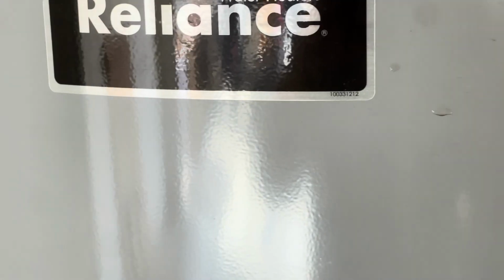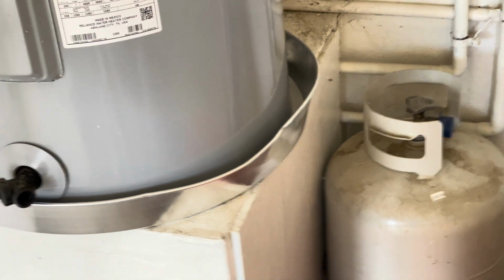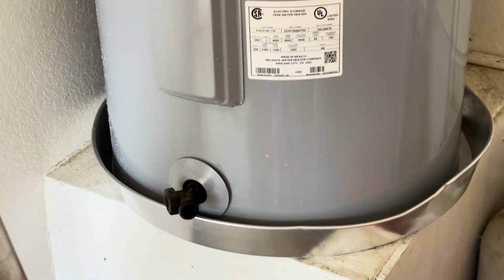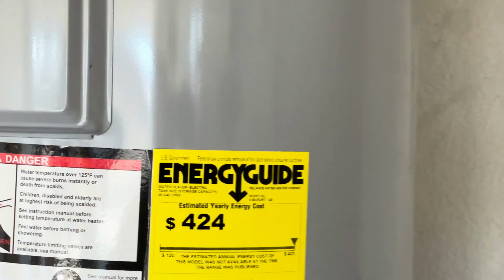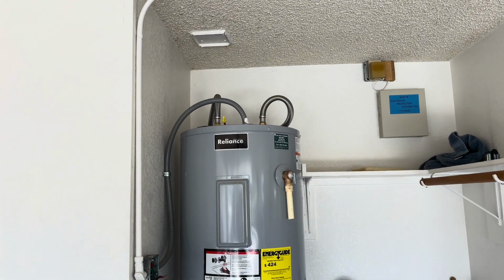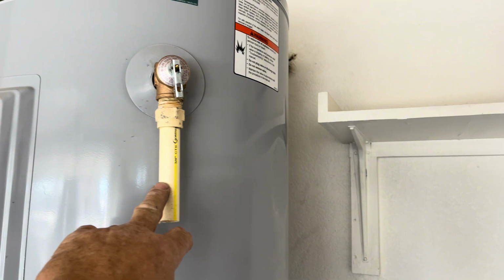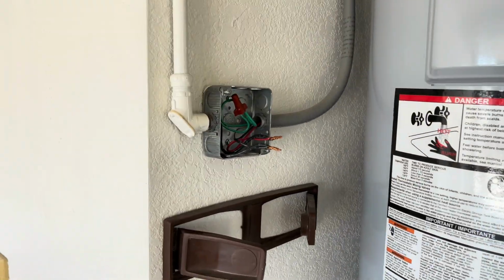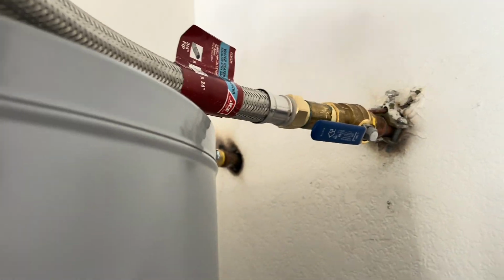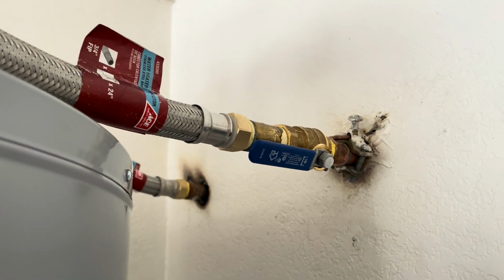Put a little bit of a different setup at the bottom of the pan. The pan is different. They didn't have a pan before, which is why it's different. And the pressure relief valve will return around to the back over here. Other than that, she's going to fit, which I had forgotten about the height. Okay, folks, everything is good, except again, I have to tie in the overflow. They want 3/4, I'll angle it over here. No power. They're not getting 220. Everything else is fine and dandy. We're looking supreme, which I love.